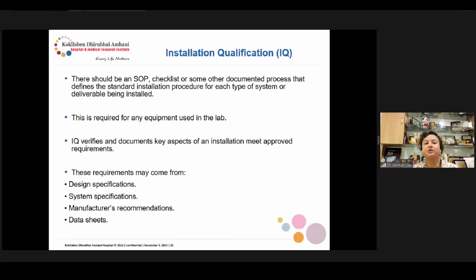Now for IQ, there should be an SOP, checklist, or some other documented process that defines the standard installation procedure for each type of system or deliverable being installed. These requirements may come from design specifications, system specifications, manufacturer's recommendation, and data sheet. So IQ verifies and documents that key aspects of the installation meet approved requirements.